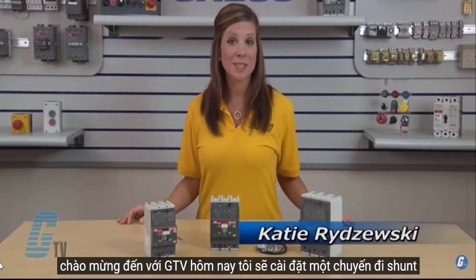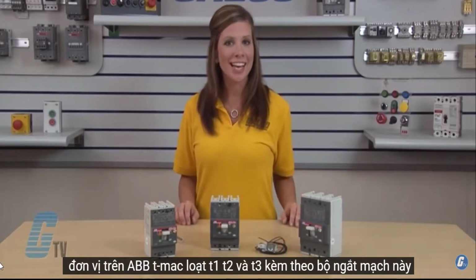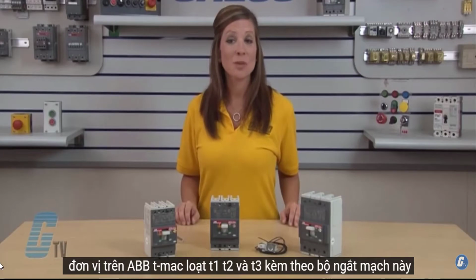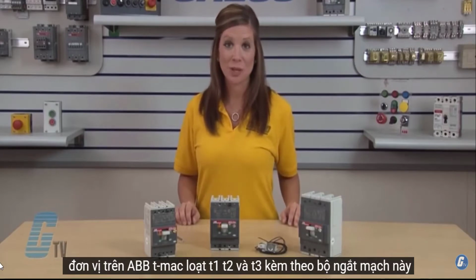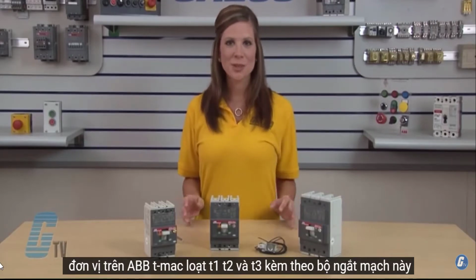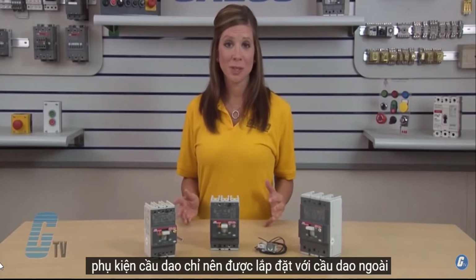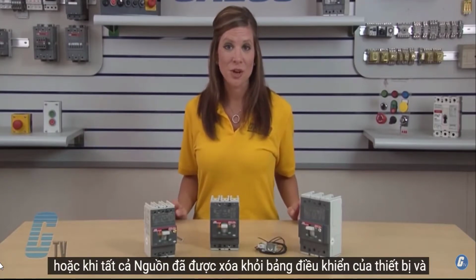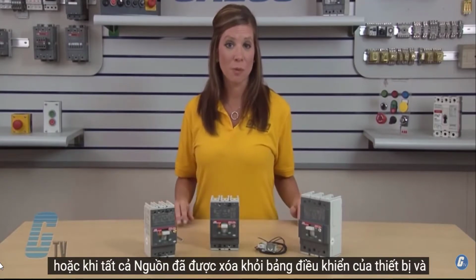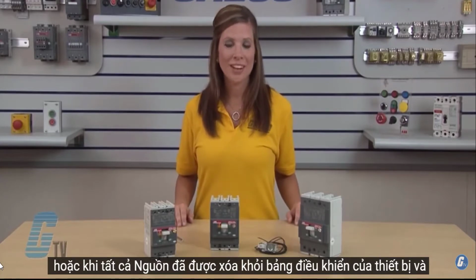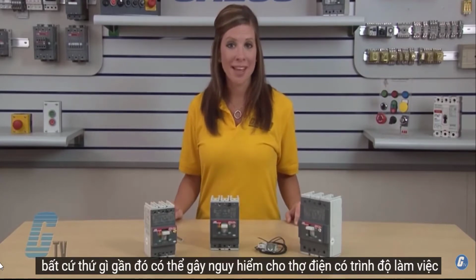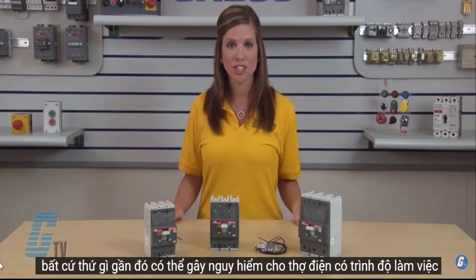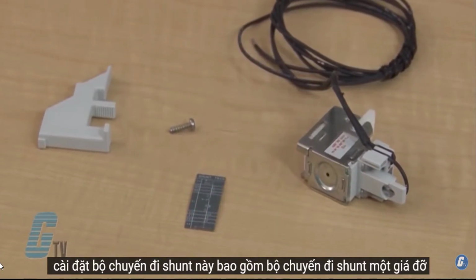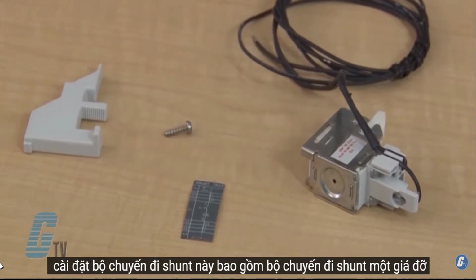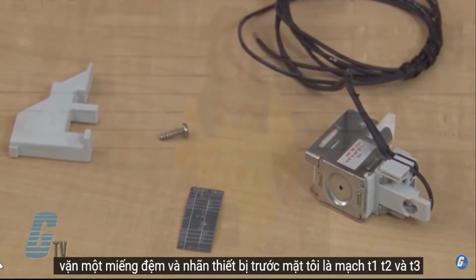GTV. Today I will be installing a shunt trip unit on an ABB TMAX series T1, T2, and T3 enclosed circuit breaker. These circuit breaker accessories should only be installed with the breaker out of circuit, or when all power has been removed from the device, control panel, and anything nearby that may be a hazard to the qualified electrician doing the installation. This shunt trip kit includes the shunt trip unit, a mounting screw, a spacer, and device labels.